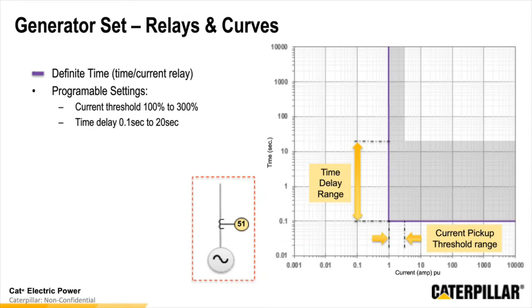So let's talk about those relays a little bit. The generator set relay that we discussed before, the 51 AC time over current, has multiple settings within it that we're going to need to make a decision on how we set up that relay. The first set point is the definite time setting. This is, as it states, you set a current setting and a current threshold. So typically you have between 100 to 300% current that it will allow. And then you set a time delay. So in this instance, we have 1/10 of a second up to 20 seconds.